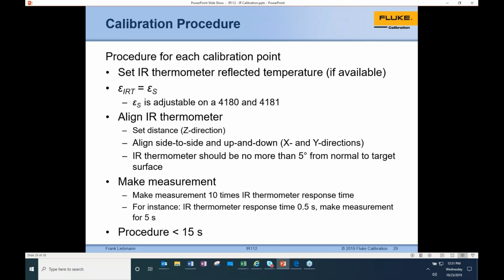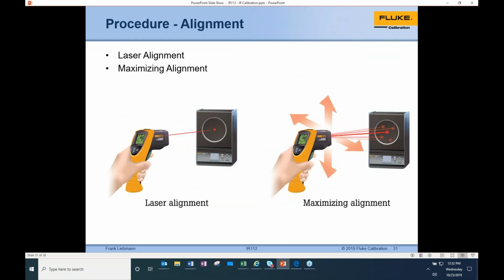So then you make your measurement. The fun part about IR measurements is it's not like some of the other temperature measurements where you have to wait. Once you pull the trigger on the gun, it's fairly instantaneous. But even with a longer IR thermometer, say you have a response time of 0.5 seconds, maybe keep it held in there for 5 seconds, just a rule of thumb. Sometimes you'll want to take multiple readings and average them just to make sure you're not getting something that's going weird within the electronics of the gun. This slide is the one I was touching on with the axis of leaning in, down, left, right, you're going to cause some deflection. So you want to be straight on as best you can to get consistency in the readings you're taking.